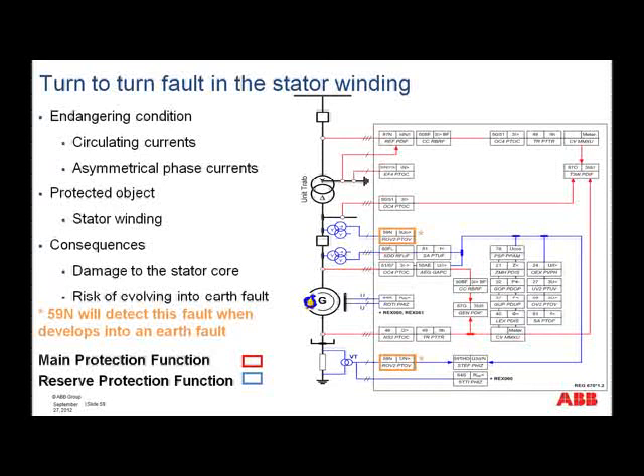Now, turn-to-turn fault in the stator winding. Traditionally, the 87G may not be able to see this. So one scenario, of course, is to wait. Nothing will happen, and if this fault should develop into an earth fault, then you have those functions which we discussed already, which would be able to detect it as an earth fault on the stator winding.